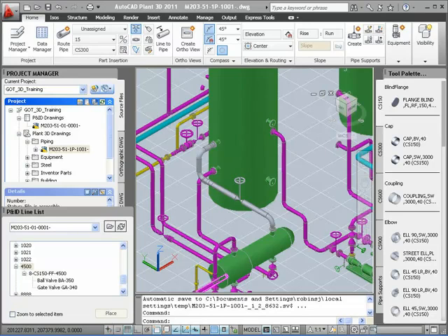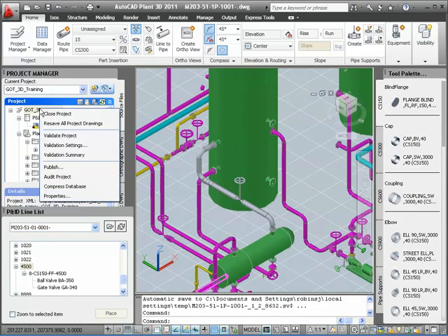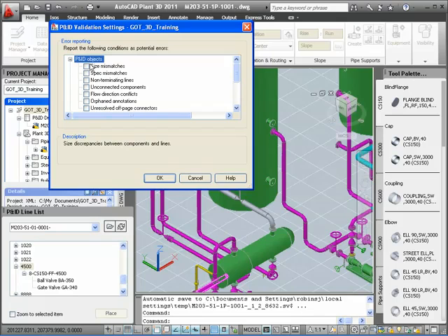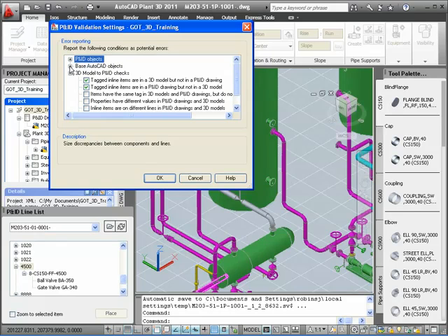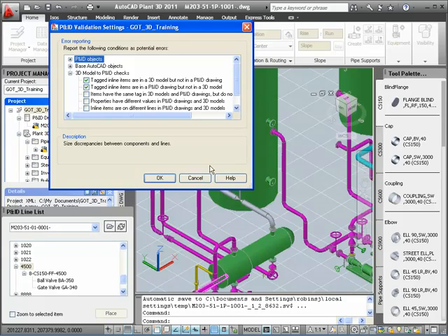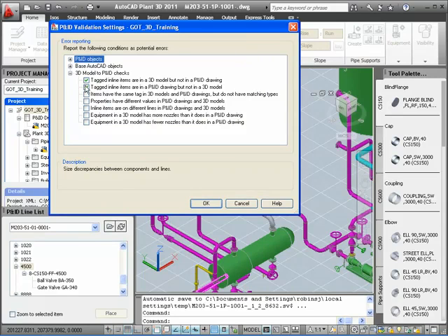Now let's take a look at validation. In a perfect world, the P&ID drawing would be complete and final before the 3D modeling began. But of course in the real world, timing is always somewhat overlapping, making it very easy to have mismatches between the two types of drawings. Here I'll right-click on the Project Manager and show you the validation settings. The first set is strictly for P&ID, the second set for AutoCAD, and finally a third set specifically to find issues between P&ID and Plant 3D — tag mismatches, items existing in one drawing and not the other, and so on. We'll test out the first two items regarding tags.